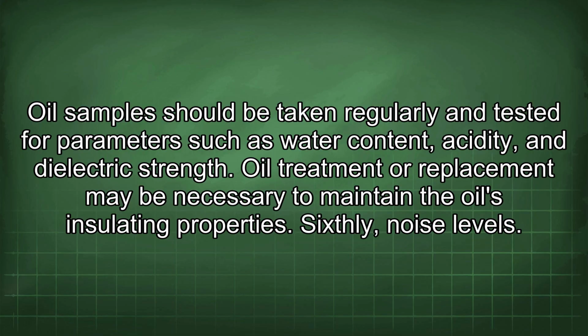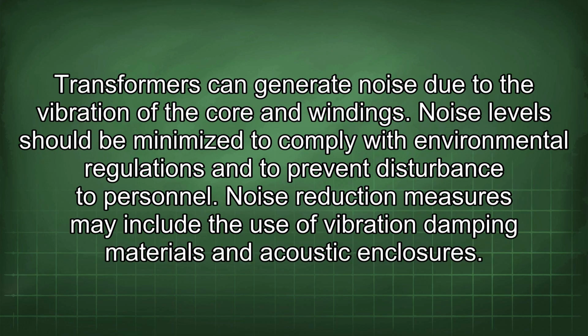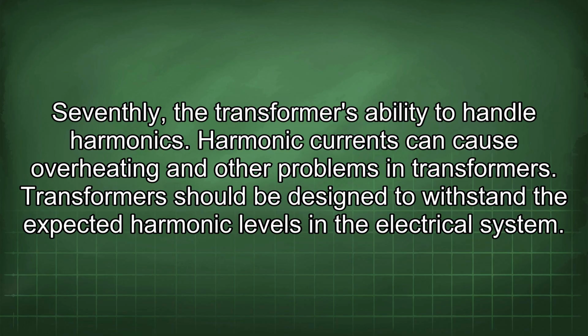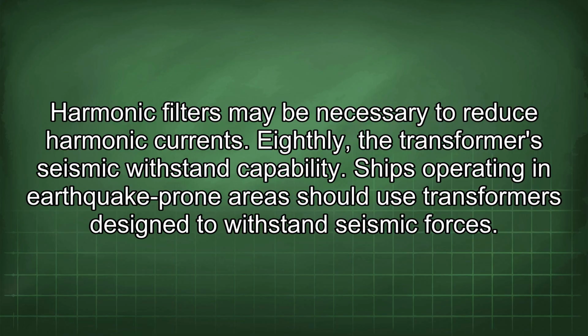Sixthly, noise levels. Transformers can generate noise due to the vibration of the core and windings. Noise levels should be minimized to comply with environmental regulations and to prevent disturbance to personnel. Noise reduction measures may include the use of vibration damping materials and acoustic enclosures. Seventhly, the transformer's ability to handle harmonics. Harmonic currents can cause overheating and other problems in transformers. Transformers should be designed to withstand the expected harmonic levels in the electrical system. Harmonic filters may be necessary to reduce harmonic currents.